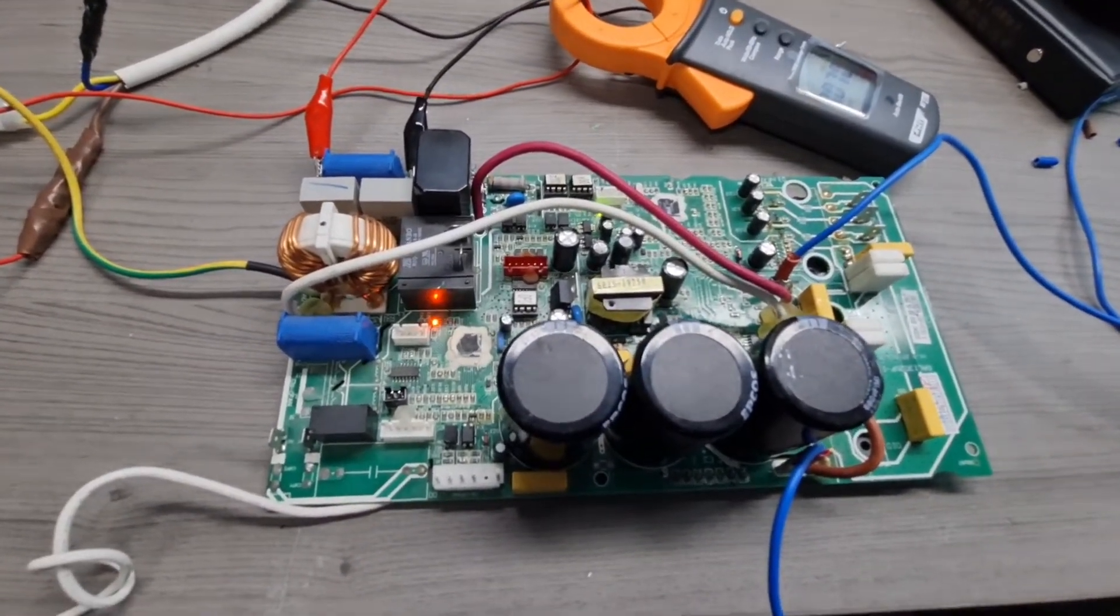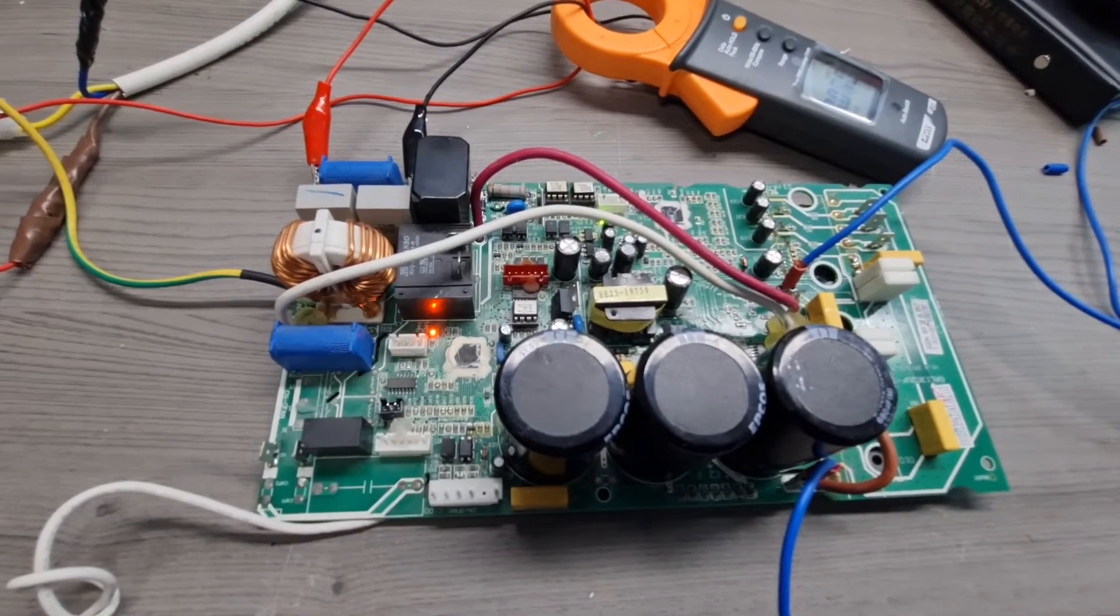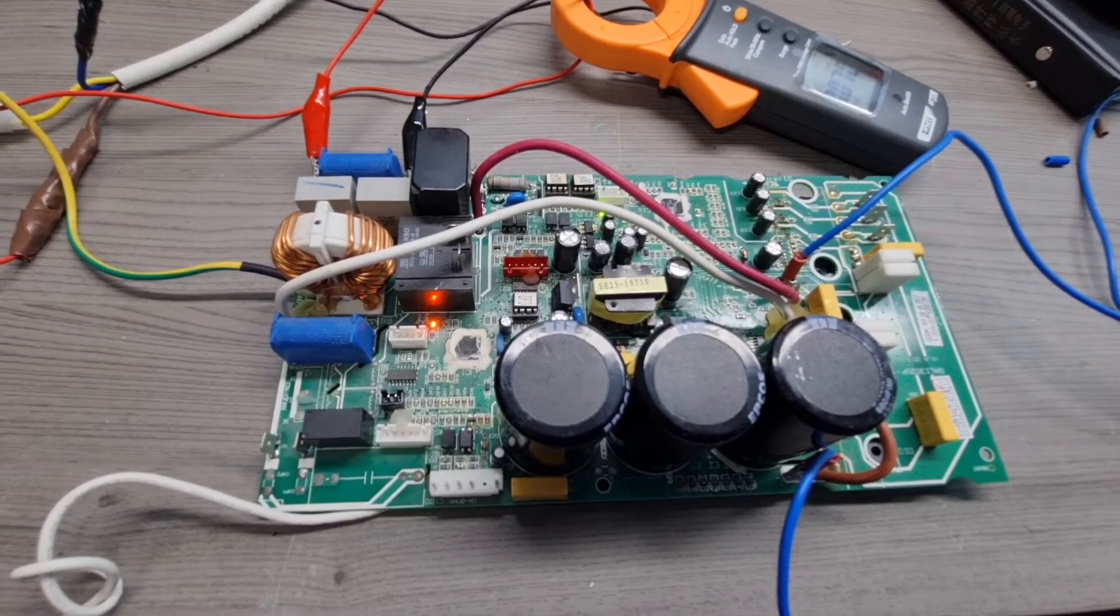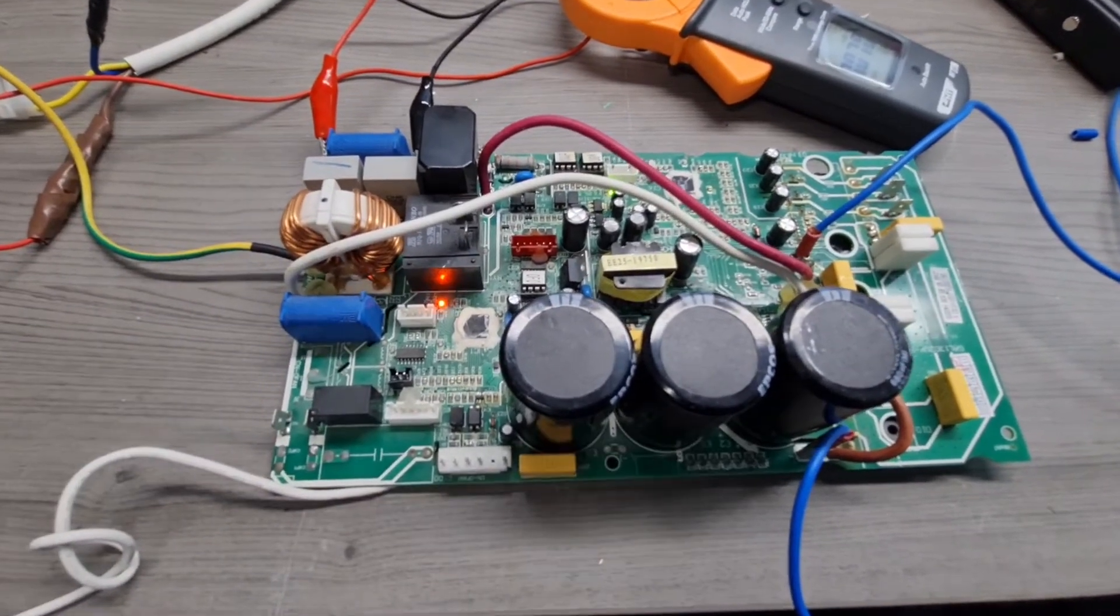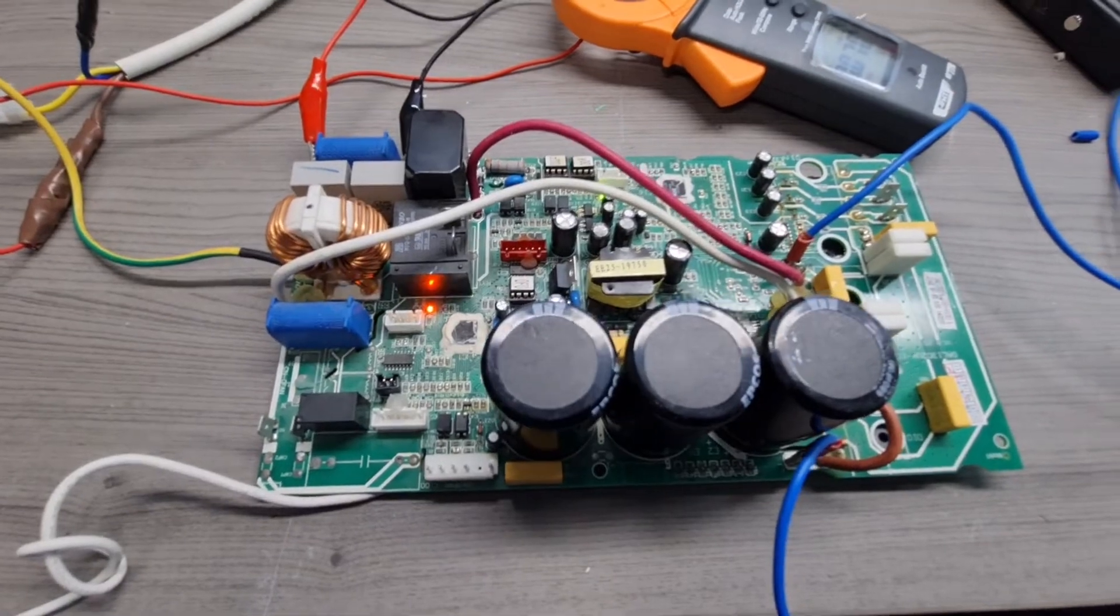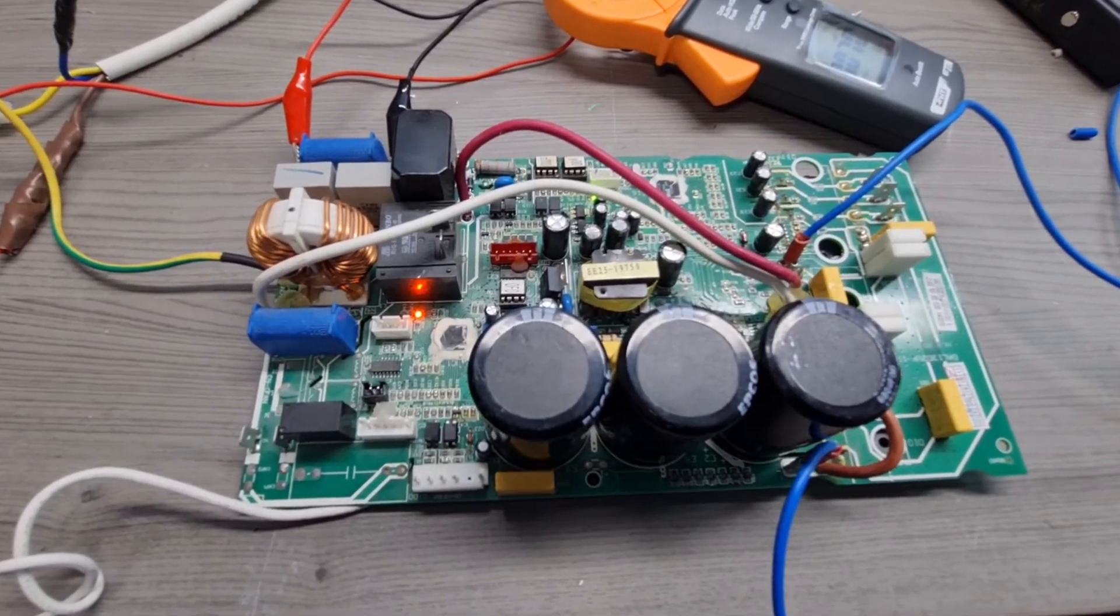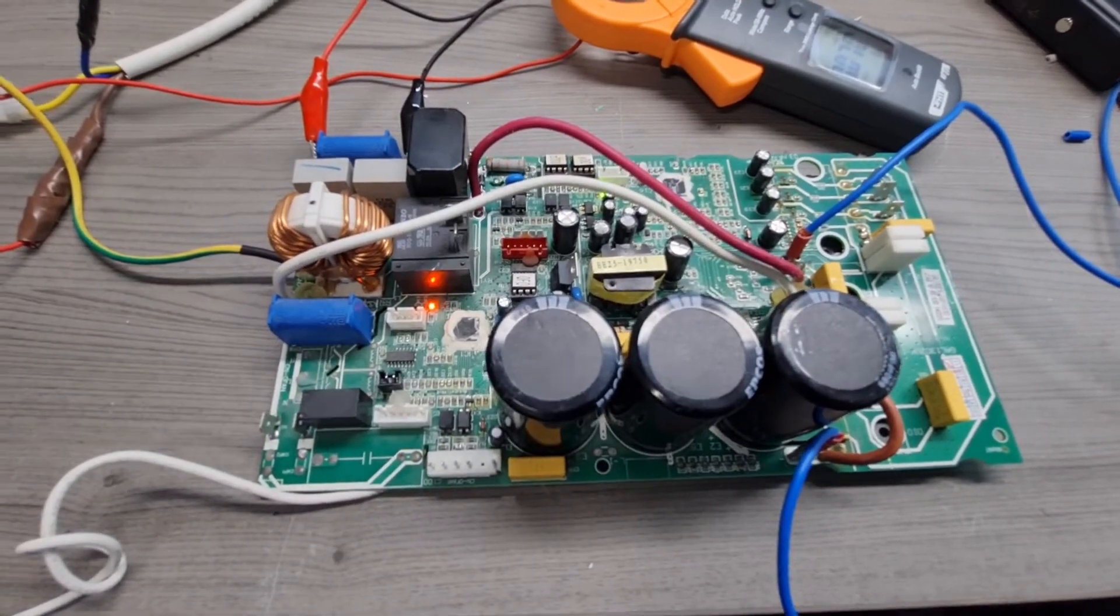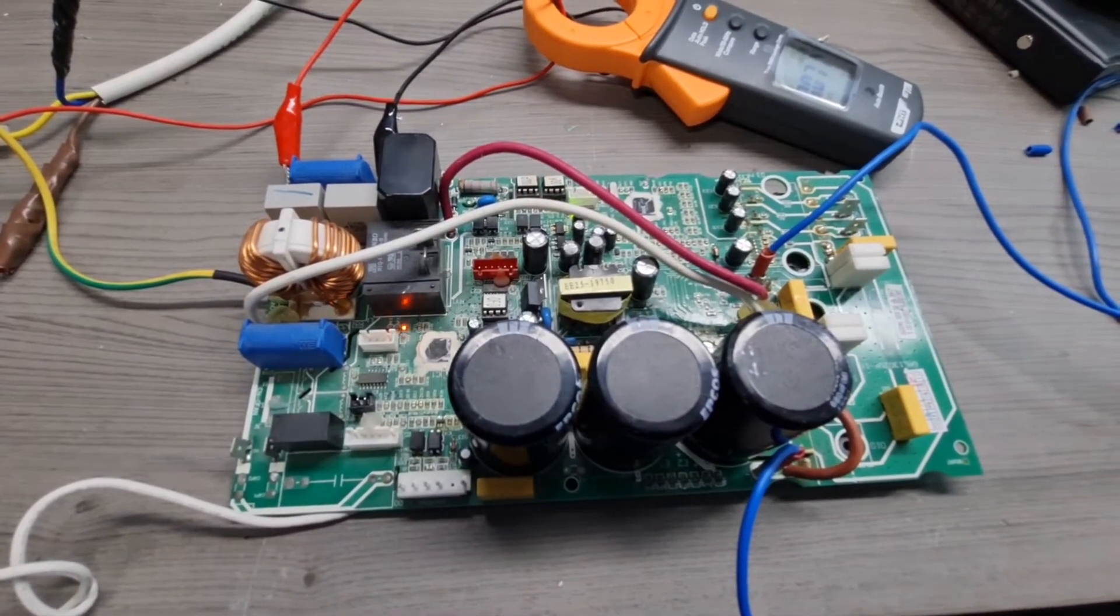Obviously one would have to also test the effects of having the compressor and the fans running, but at least we have identified one of the contributors to leakages which are those Y capacitors at the input of the power supply.